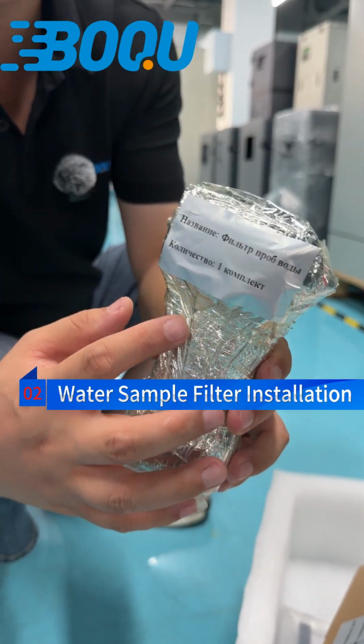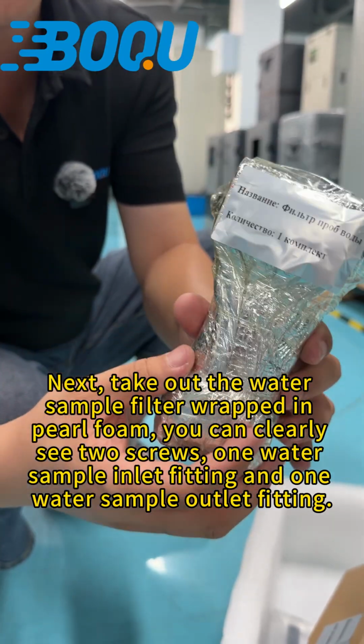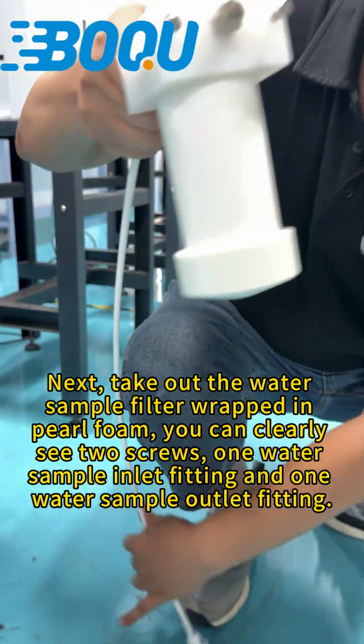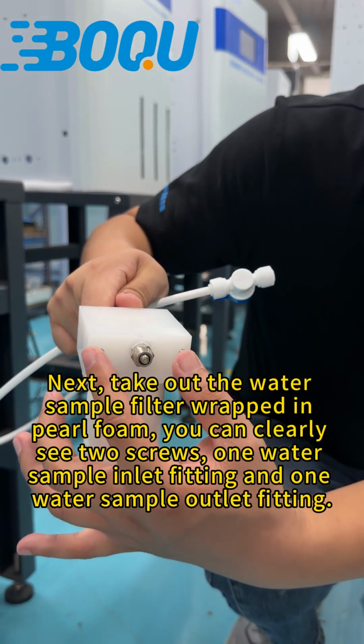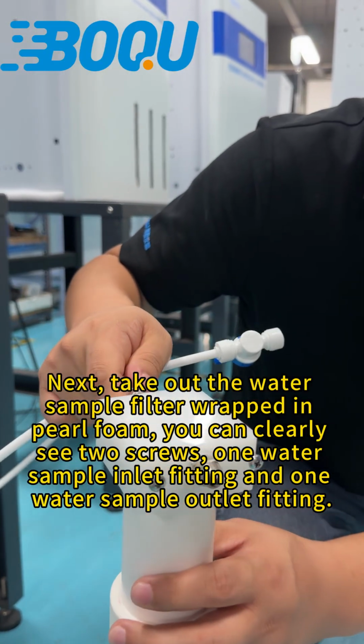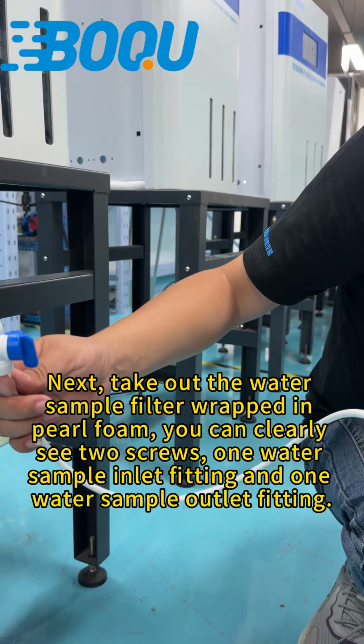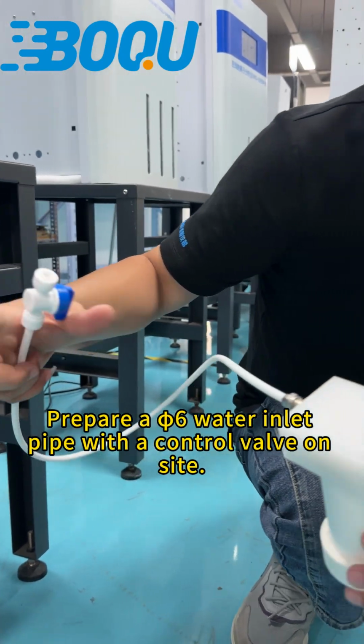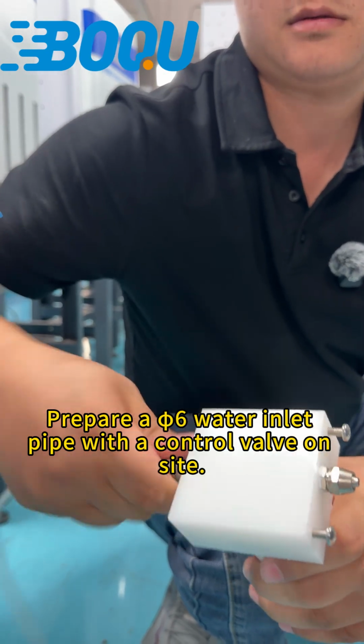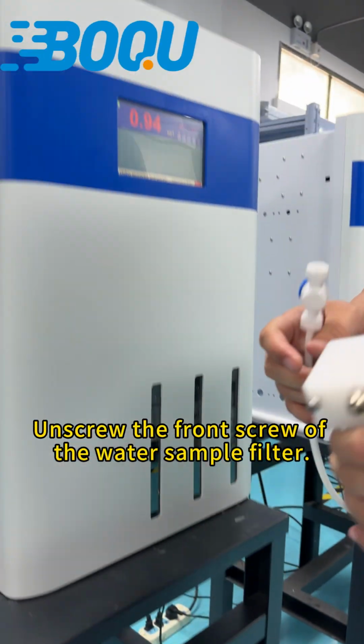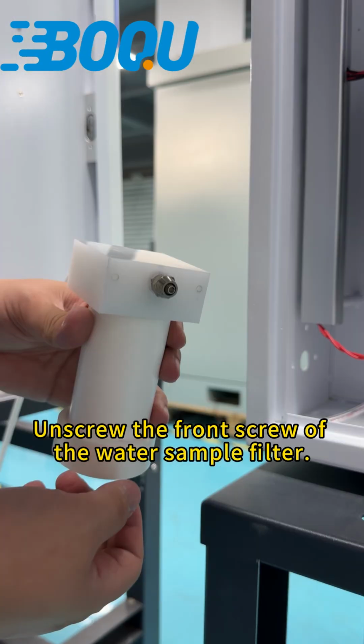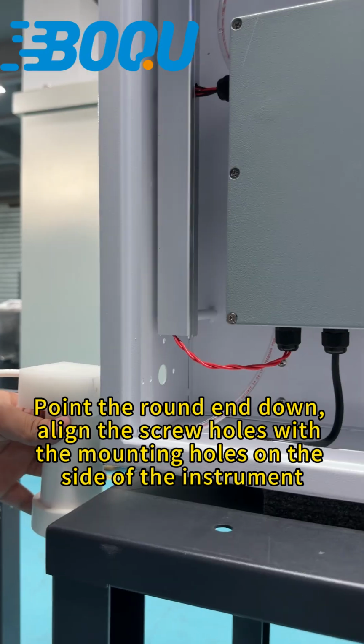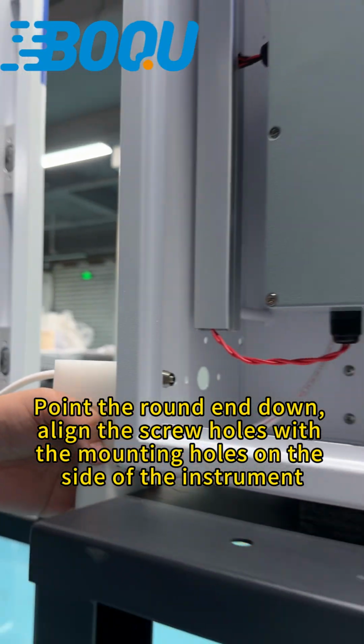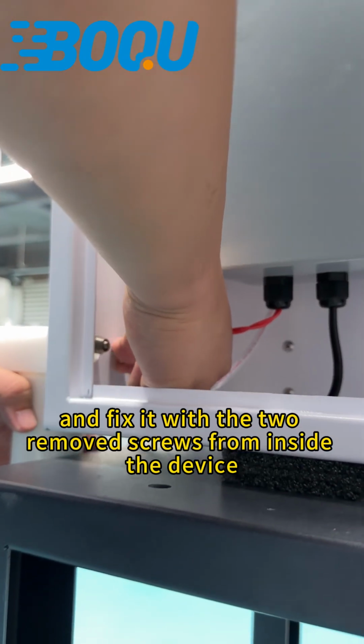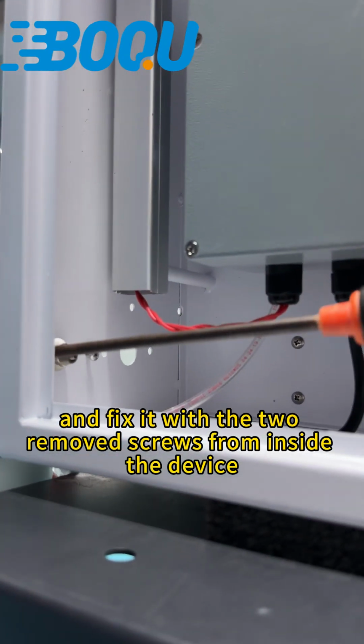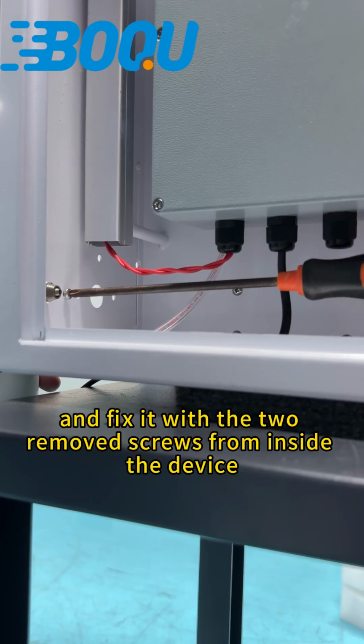Water sample filter installation. Next, take out the water sample filter, wrapped in pearl foam. You can clearly see 2 screws, 1 water sample inlet fitting, and 1 water sample outlet fitting. Prepare a φ6 water inlet pipe with a control valve on site. Unscrew the front screw of the water sample filter. Point the round end down. Align the screw holes with the mounting holes on the side of the instrument, and affix it with the 2 removed screws from inside the device.